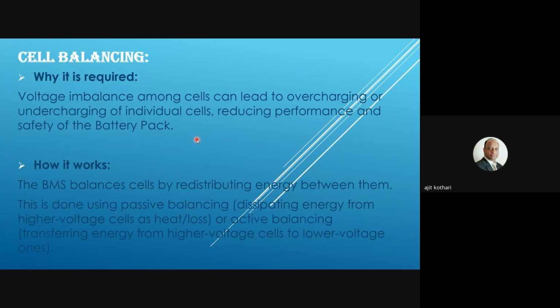Now let's understand this from the charging point of view. Again consider two cells connected in series, one 100% charged, another 50% charged. Once you connect the charger, since the first cell is already fully charged, the charging current gets limited to the float current. This means the battery pack doesn't get full rate charging current, because the first cell is blocking that current since it's already full.